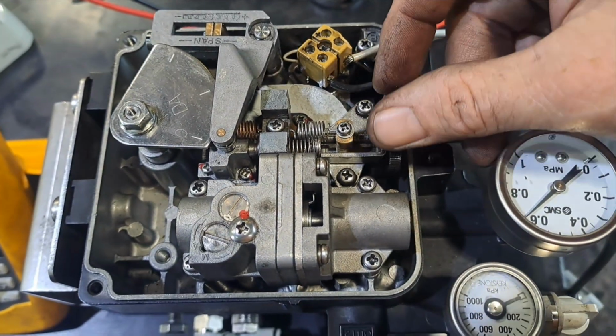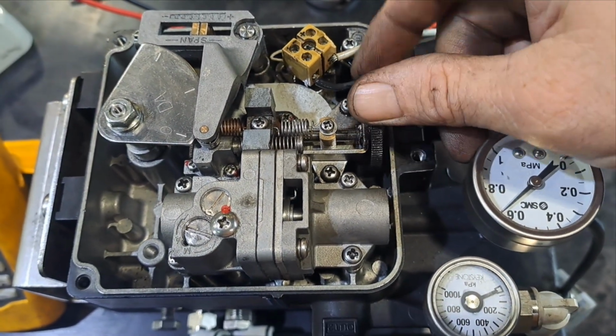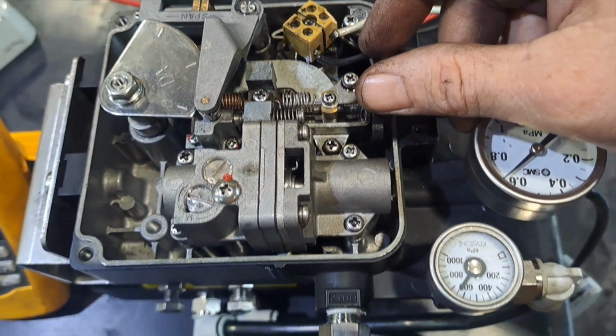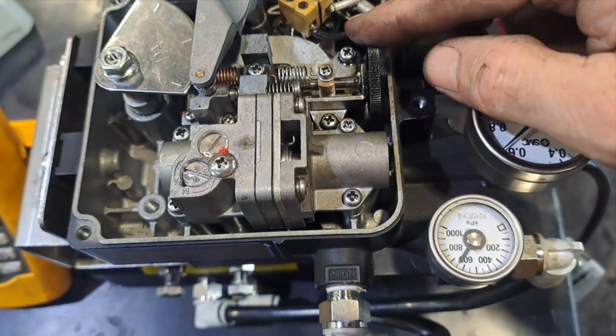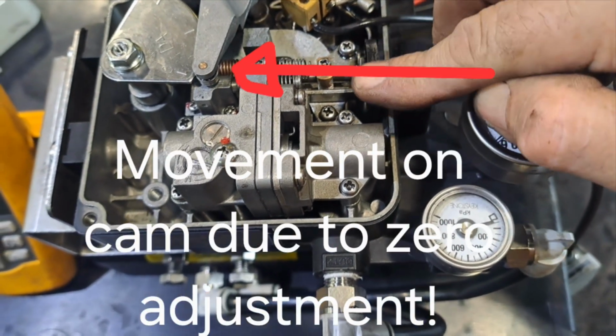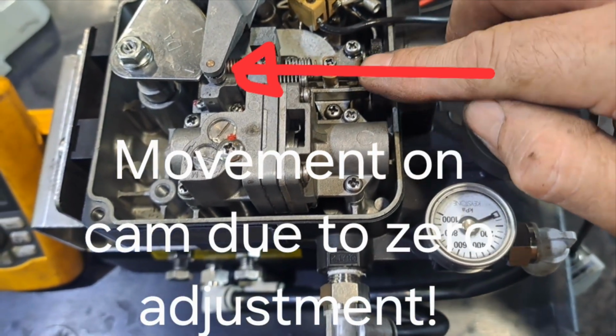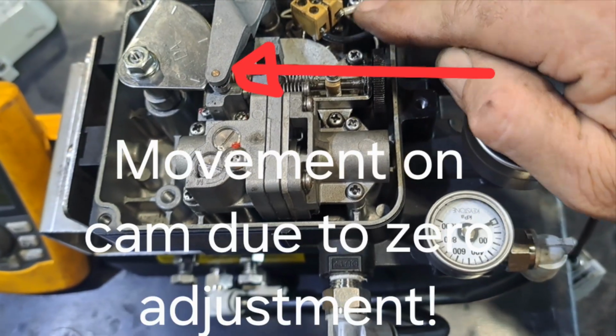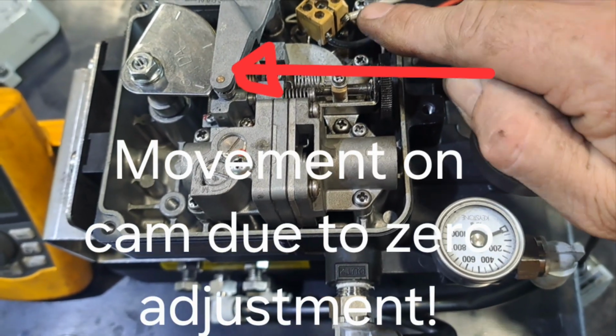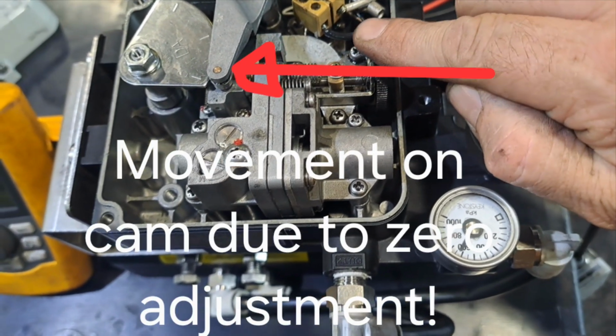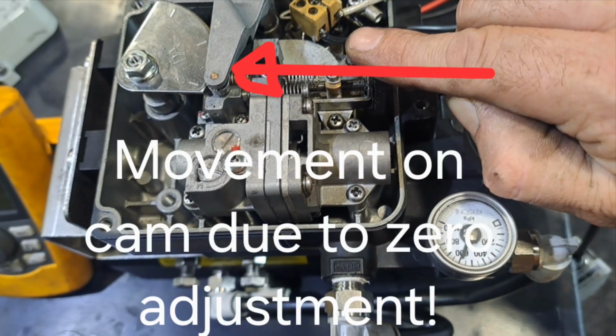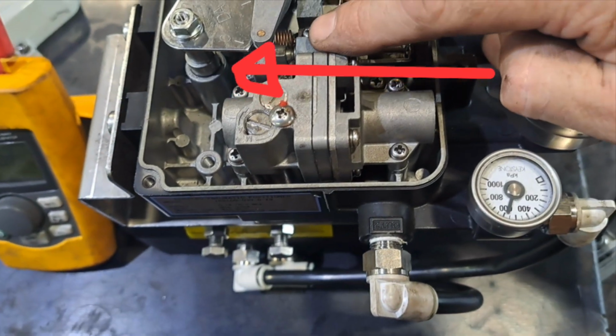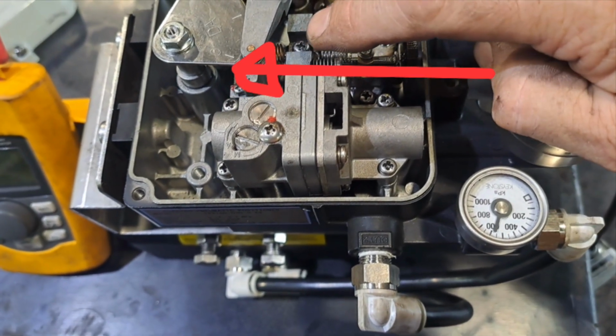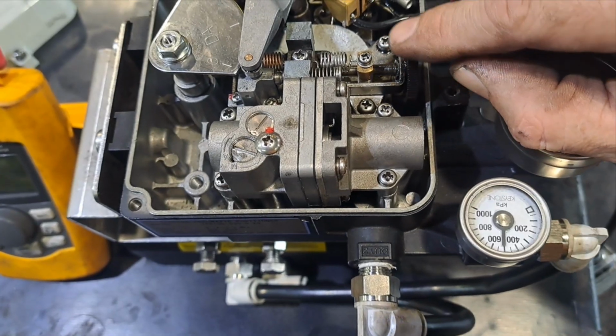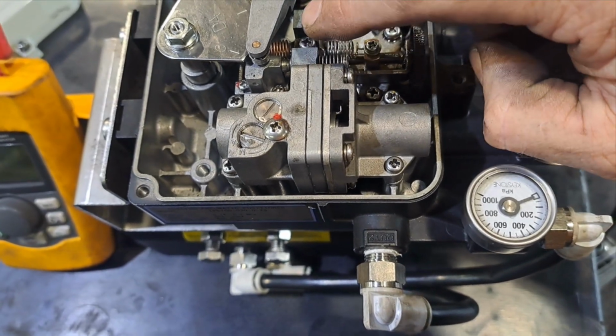Now, as you can imagine, the 0 position will be off. And also, because the movement is in a different direction, the 0 will be off from the cam plate. So we have to re-zero and find that 0 again. If you just add your 4 to 20 milliamps at this point, it might not work properly, it might just swing around, and it might not find the right spot. So we have to zero it first.